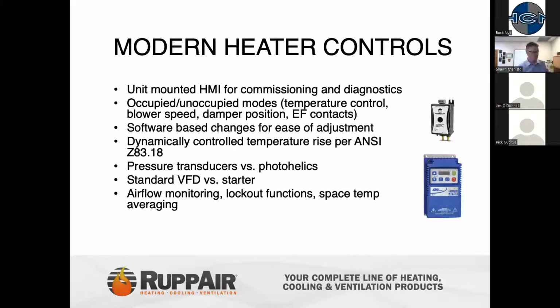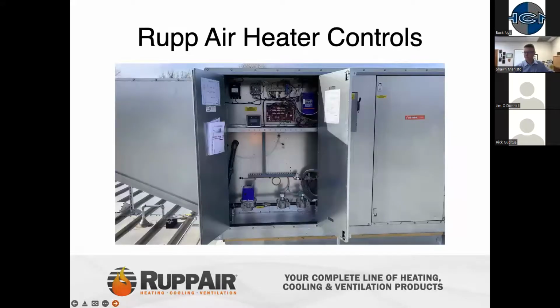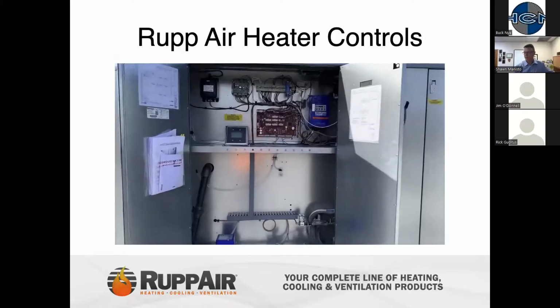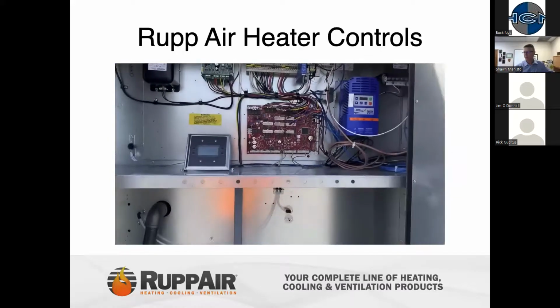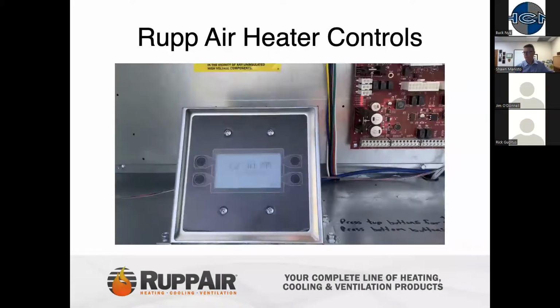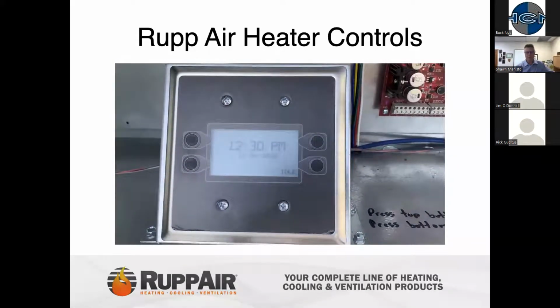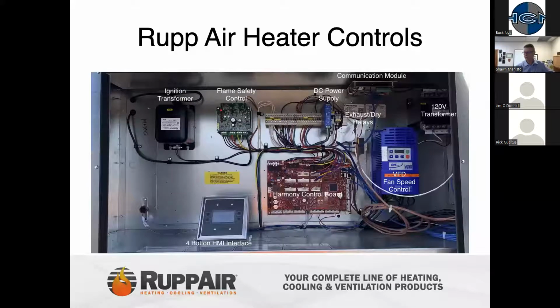Other things we've incorporated into the modern heaters today is moving away from things like mechanical photohelics into pressure transducers. VFDs are kind of a standard across the board on all products, making sure you have that flexibility, like I said, not only of burner modulation, but also of fan modulation. This is just an image of one of our Rupp Air direct fired heaters, kind of doing the walk up here. This is our main control board. This is one of our touchscreen pads that our technicians use when they do setup and commissioning of the equipment. Just another little image of kind of how things have been cleaned up and compact, no more of the old.